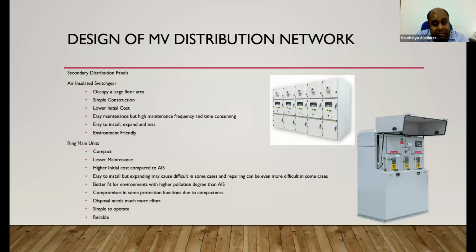Ring main units: compact, very compact. Lesser maintenance if it's with gas insulation. Higher initial cost compared to AIS sometimes. Easy to install, but expanding may be difficult in some cases, and repairing can be even more difficult in some cases. If you find a gas leak in an SF6 chamber, that's unrepairable. You will have to replace the whole switchgear arrangement.